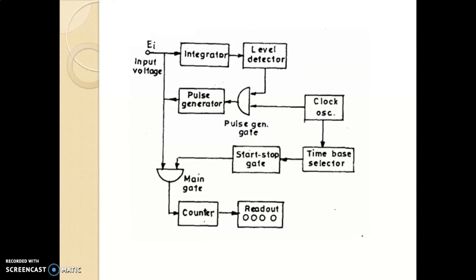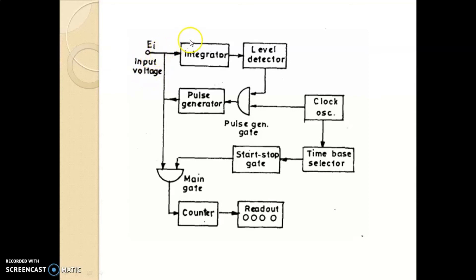Let's see another block diagram of the integrating type of digital voltmeter. This block diagram has two parts. In the first section, it is a frequency generator. In the second section, we have the input voltage measurement. The input voltage to be measured is applied to the integrator, and the output of the integrator goes to the level detector or comparator, which will change state continuously so that the pulse generator generates pulses at a regular interval.